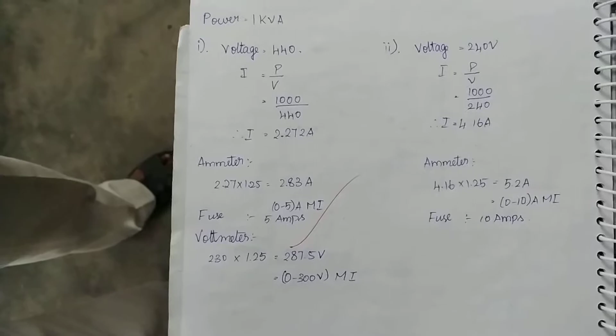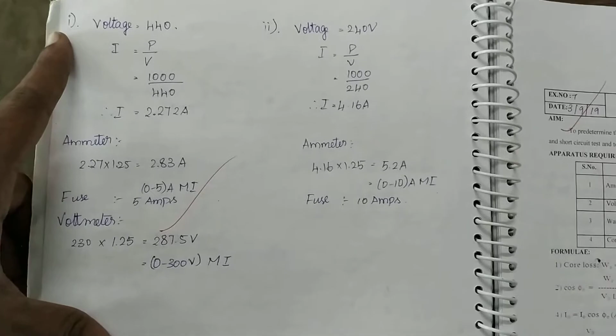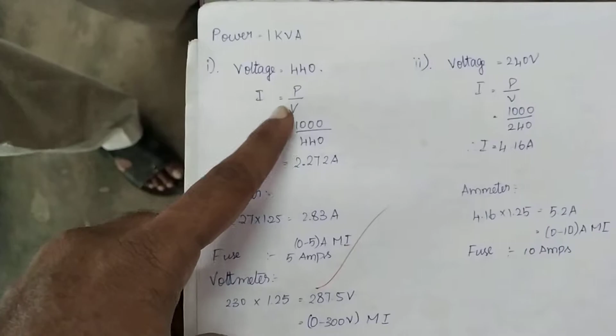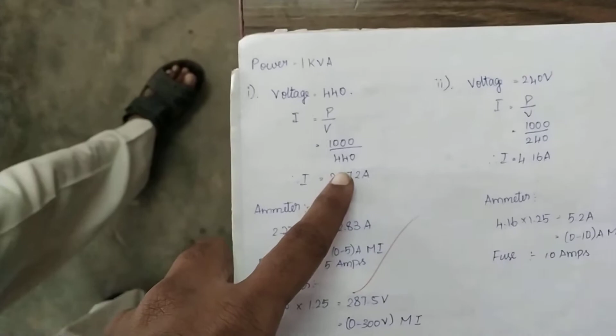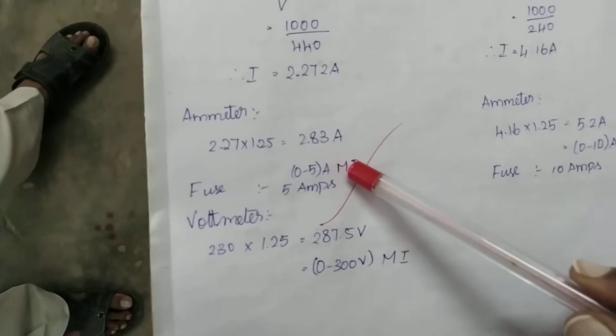So for this test, you have to again calculate the range. You are connected to the high voltage side, correct, so current can be calculated as power divided by voltage. Power is 1000, that is 1 kVA, and voltage is 440. So you will get current equal to 2.27. What is the meter nearest to this value? That is 0 to 5 amps. So you have to select a 0 to 5 amps MI, and the fuse also you have to select as 5 amps.